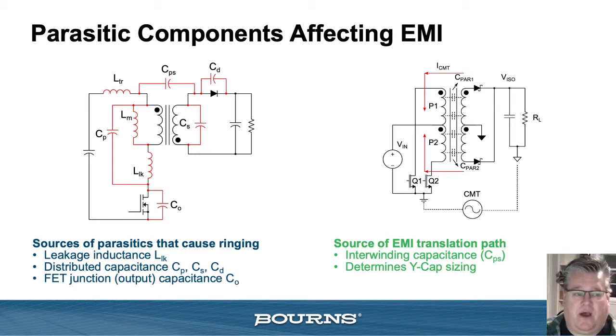So while I agree leakage needs to be kept as low as possible, other combinations of things can be used to move the self-resonant frequency of the transformer out of the region of transient effect, to reduce that.